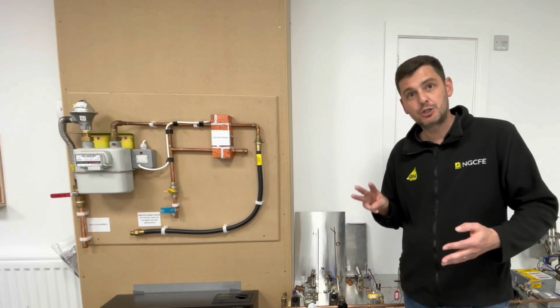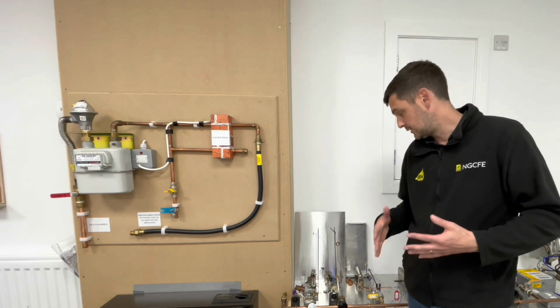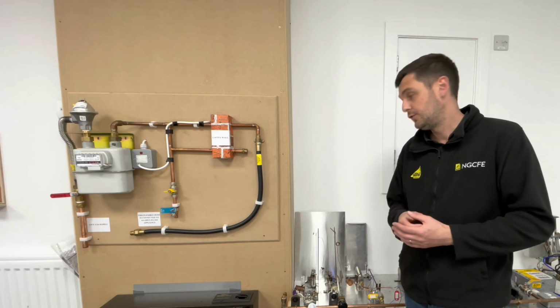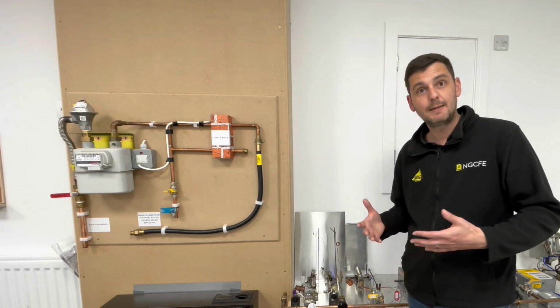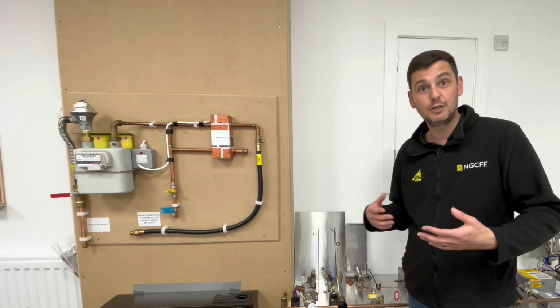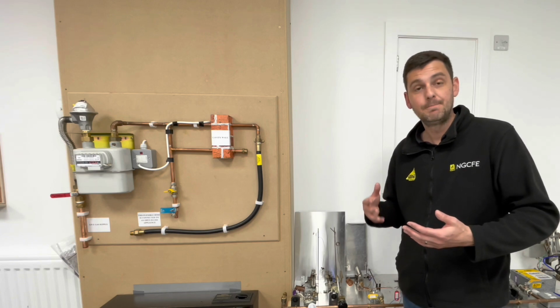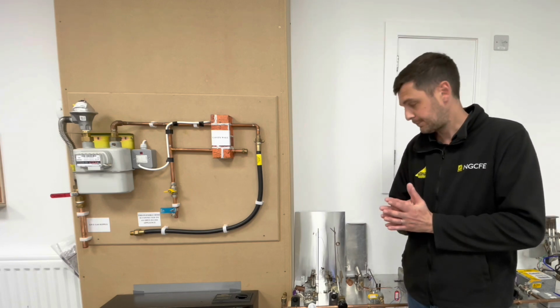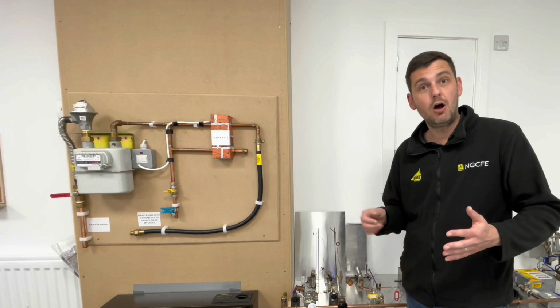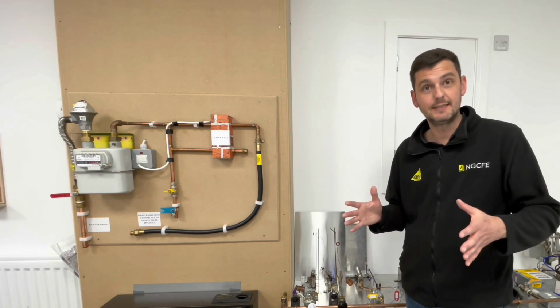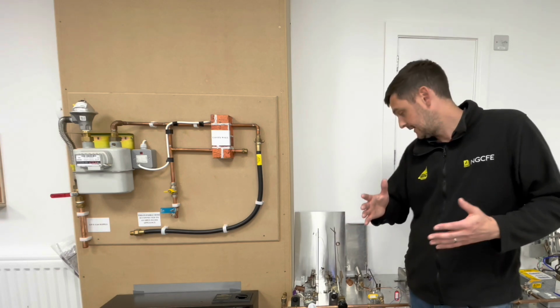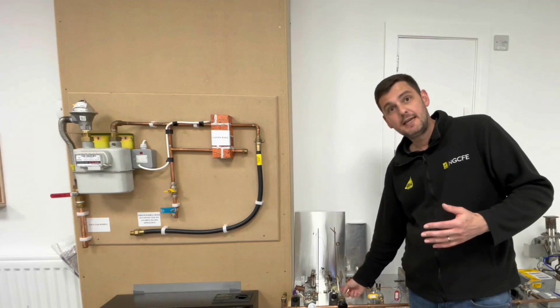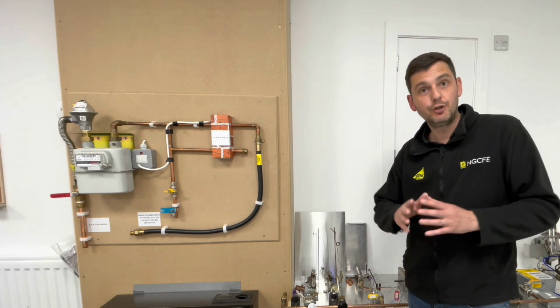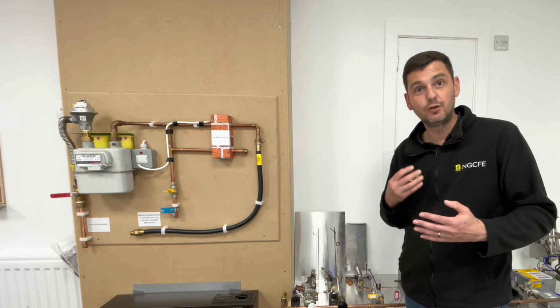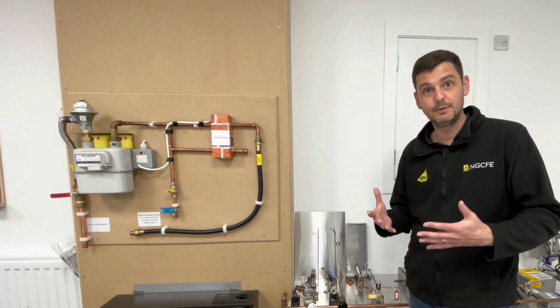Now there's 3 possible faults associated with this type of appliance. So if you're ever called out to one of these older type cookers with a liquid expansion FSD as well as a liquid expansion thermostat, the 3 things we need to be aware of. First fault is you can't light the oven, it just won't light. If that's the case, it means that the bypass in the FSD is blocked, so you're not getting any gas through to the burner, even to light on a low flame.